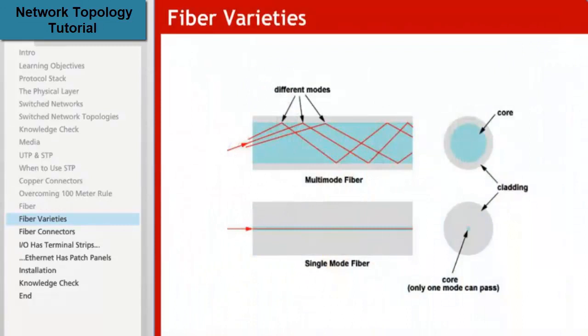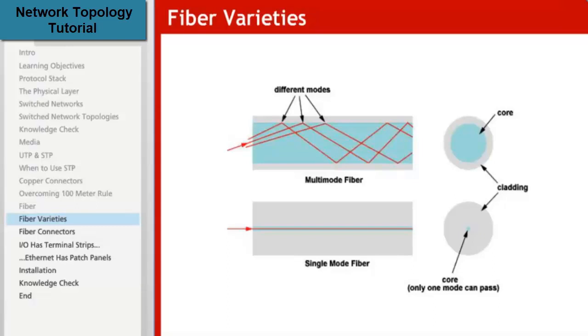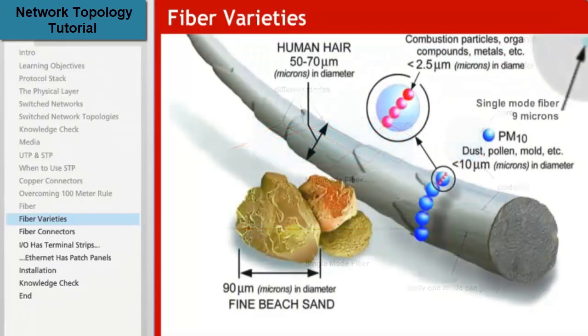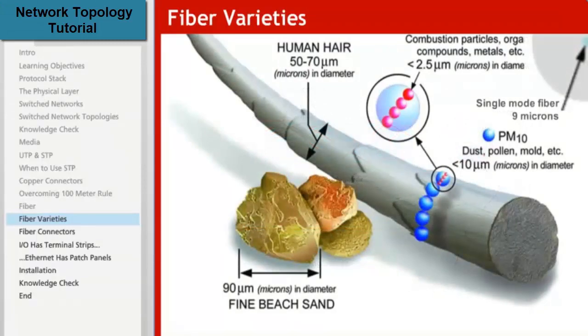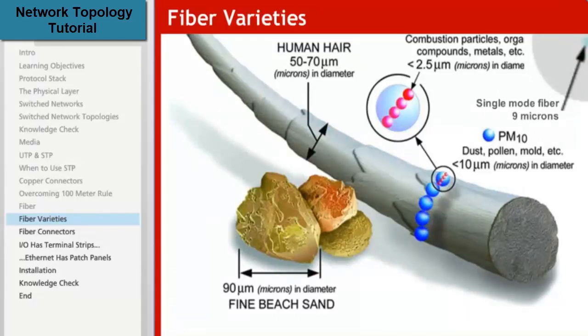Fiber optic cable is available in two types, single mode and multi-mode. Both types of cables are generally 125 microns in diameter, but the fiber core itself that guides the light waves varies in size. Single mode fiber cable carries a single light wave and is a very efficient low-loss cable. It is manufactured with a 9 micron fiber core that is capable of runs up to 10 kilometers. Multi-mode cable is less expensive and carries multiple light waves through its much larger 50 or 62.5 micron core. Multi-mode cable can be used for runs up to 2 kilometers in length.